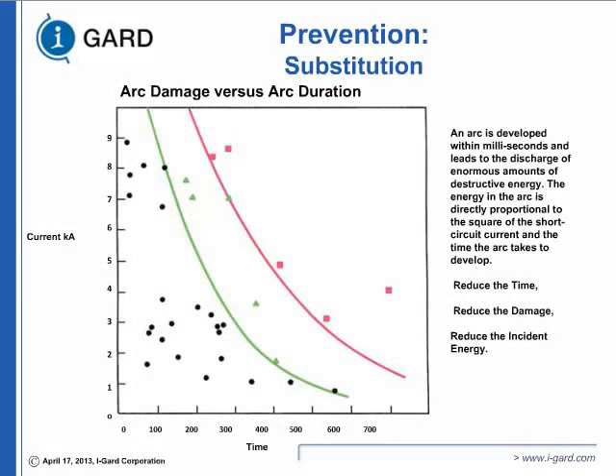This is a chart produced by Dr. Land, who did a lot of research on equipment damage. You see two lines, red and green, and you can see how many points for research he tested. If the incident energy or the heat is below the green line, equipment is probably repairable. If it's above the red line, it's probably not. You'll have major damage. So in the design stage, you want to keep everything below that green line if you can.